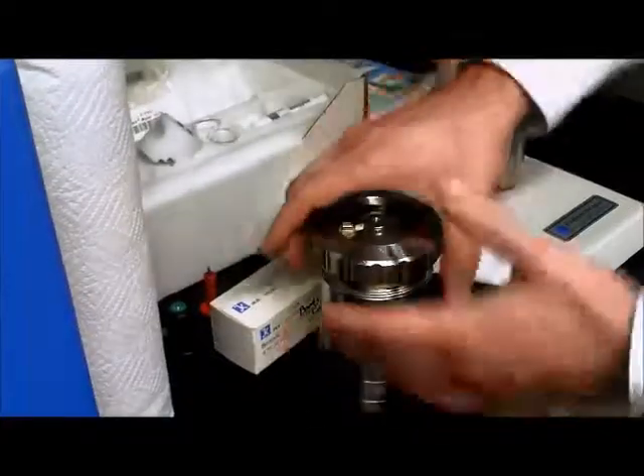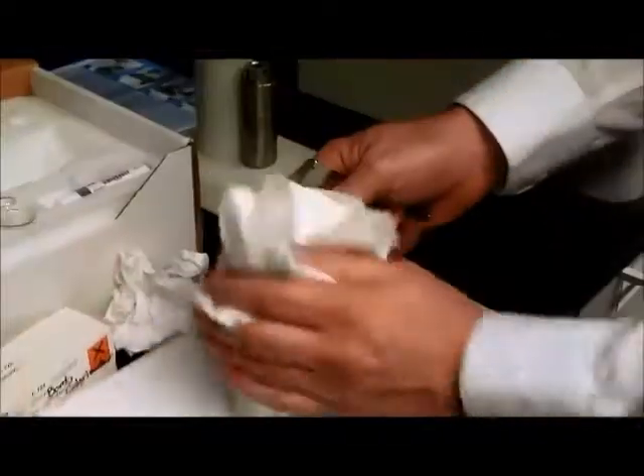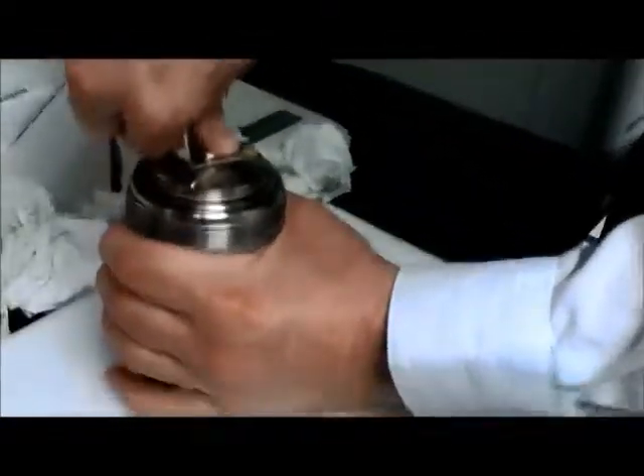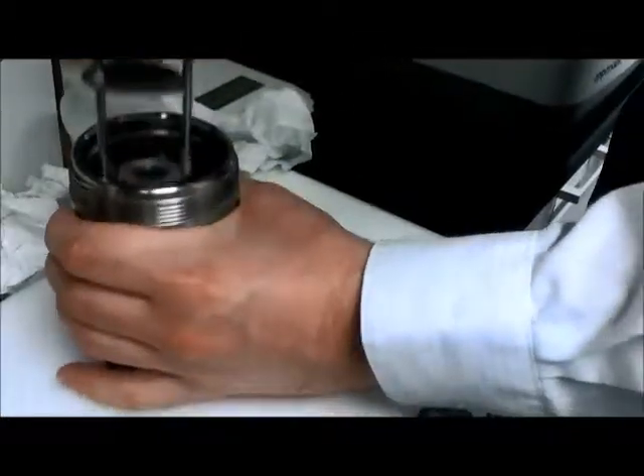All right, so once it's been relieved, it's safe to take off the union nut. Look for the union label. So then we can take off the top of the bomb again. Correct. It came out a lot easier there. Came out a lot easier because it hasn't been sitting around.